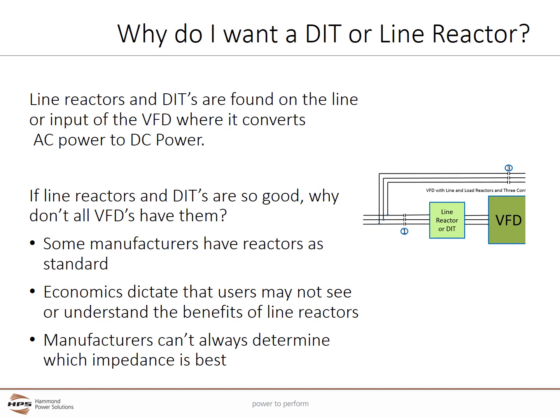First, some manufacturers actually do have line reactors as a standard VFD component. Economics dictate that users may not see or understand the benefits of line reactors and DITs. As a result, they don't see a cost-benefit justification, just like safety is not the defining factor as to why everyone buys a car. For line reactors, manufacturers can't always determine which impedance is best. DITs are much larger and more costly than line reactors, sometimes even more costly than the VFD. While DITs are often but not always superior to line reactors, their higher cost and larger size often make the cost-benefit ratio harder to justify.